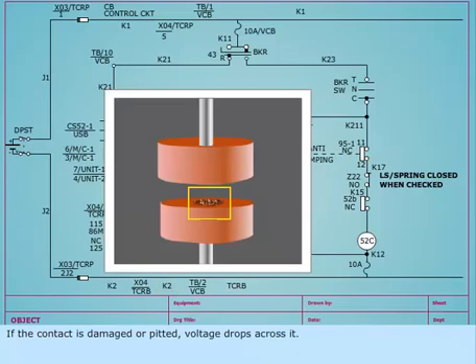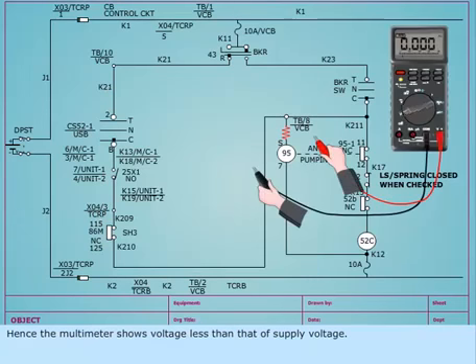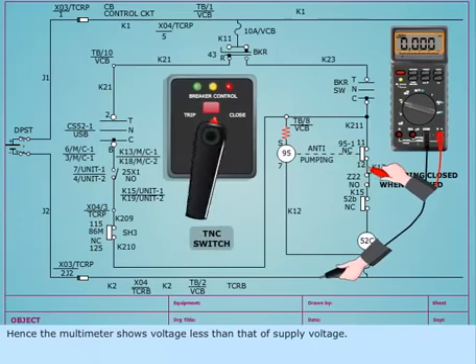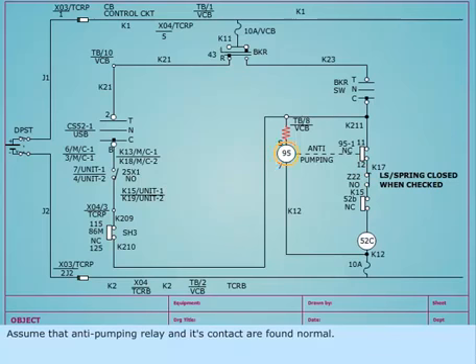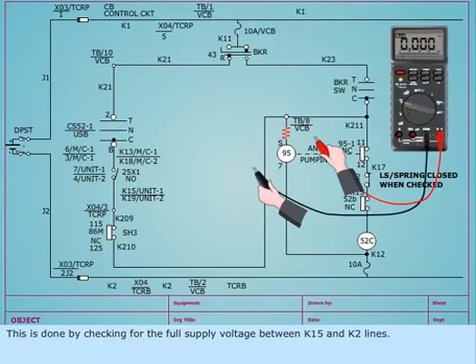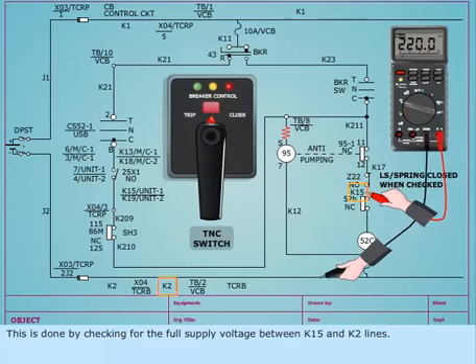If the contact is damaged or pitted, voltage drops across it. Hence, the multimeter shows voltage less than that of supply voltage. Assume that anti-pumping relay and its contact are found normal. The limit switch should be checked for healthiness. This is done by checking for the full supply voltage between K15 and K2 lines.